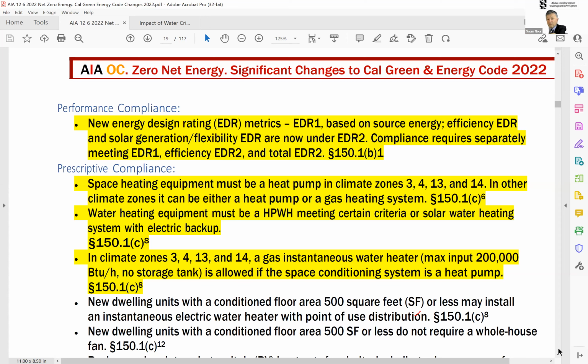So watch out—you can put a 599,000 water heater in a room and it's not 1-hour rated, but as soon as you put a boiler at a 200,000 rating, it shall be 1-hour rated with all the sophistications you all know as an architect for what goes in a 1-hour rated room. So you can have a gas instantaneous water heater, it's allowed if the space conditioning system is a heat pump. Now they are simply saying, I want to let you have a hydronic system using this system, but no more comments.